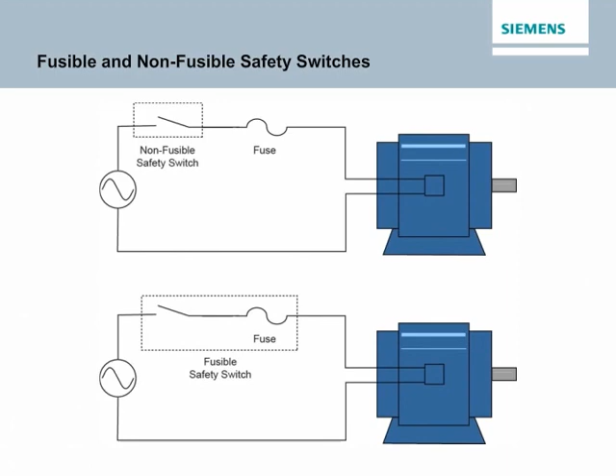Current flow in a conductor always generates heat. The greater the current flow in a given size conductor, the hotter the conductor. Excess heat is damaging to electrical components and conductor insulation. For this reason, conductors have a rated continuous current carrying capacity, or ampacity. Overcurrent protection devices, such as fuses, are used to protect conductors from excessive current flow. Fuses are designed to keep the flow of current in a circuit at a safe level to prevent the circuit conductors from overheating. Excessive current is referred to as overcurrent.